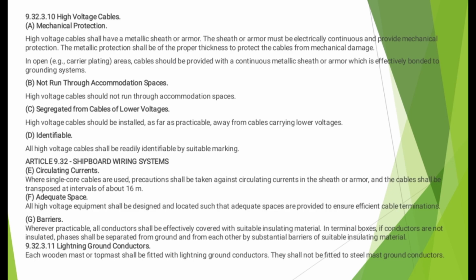Circulating currents. Where single core cables are used, precaution shall be taken against circulating currents in the sheath or armor, and the cable shall be transposed at intervals of about 16 meters. Adequate space. All high voltage equipment shall be designed and located such that adequate space is provided to ensure efficient cable termination. Barriers. Wherever practicable, all conductors should be effectively covered with suitable insulating material. In terminal boxes, if conductors are not insulated, they shall be separated from ground and from each other by substantial barriers of suitable insulating material.